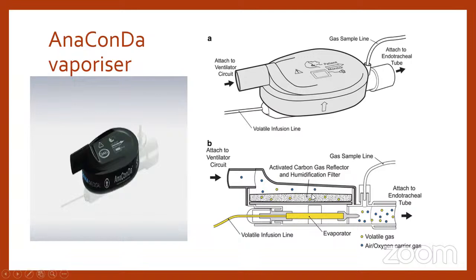So both of them will be mixed inside this chamber, and this mixture will come out of this, and there will be a gas sample, so that we can always monitor whether the mixture is mixed with agent or not, and whether the fresh gas is flowing or only the vapor is going.